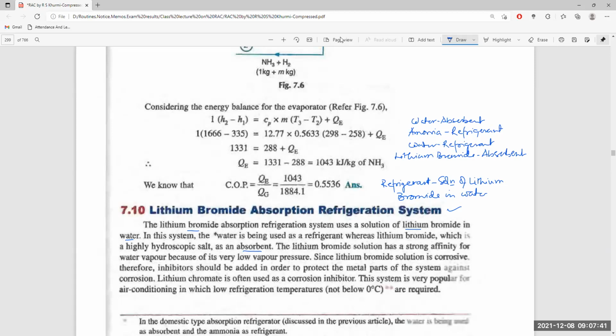Since lithium bromide solution is corrosive, some inhibitors, some protecting chemicals, should be added in order to protect the metal of the system against corrosion. Lithium chromate is found as a corrosion inhibitor. This system is very popular for air conditioning, in which low refrigeration temperatures, not below 0 degrees, are required.